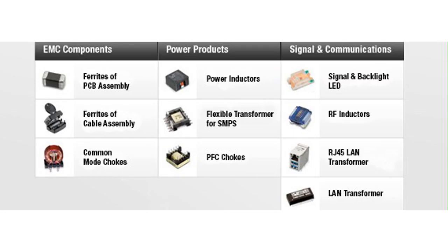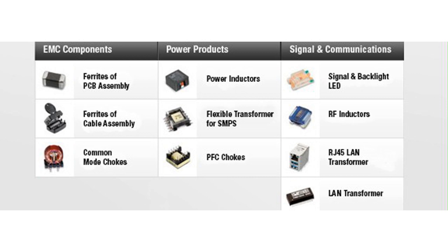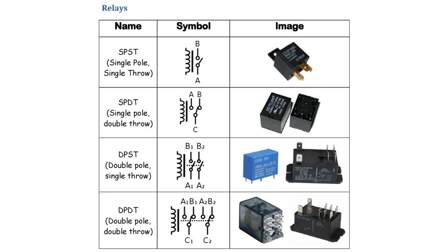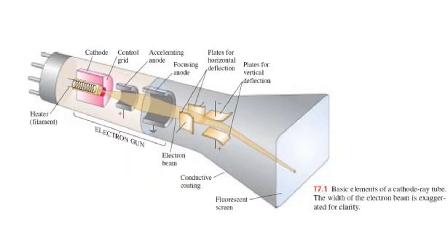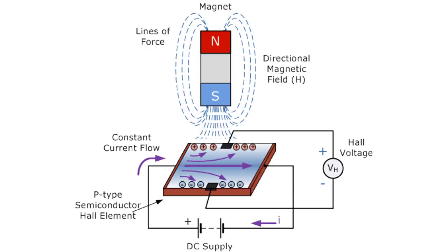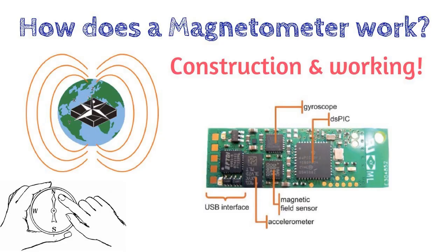There are a few types of components that can be particularly susceptible to magnetic fields. Often the test is exempted if your device does not contain any components that could perceivably be affected by a magnetic field. But here are some to watch out for: relays, CRT monitors, Hall elements, electrodynamic microphones, and magnetic field sensors.